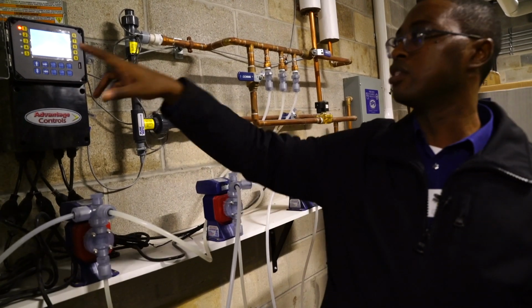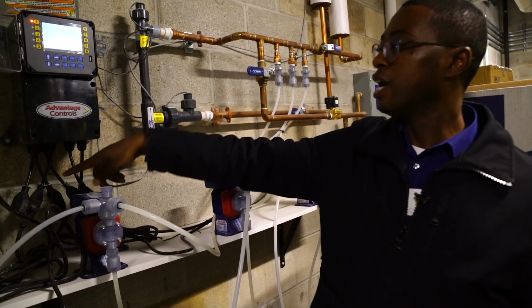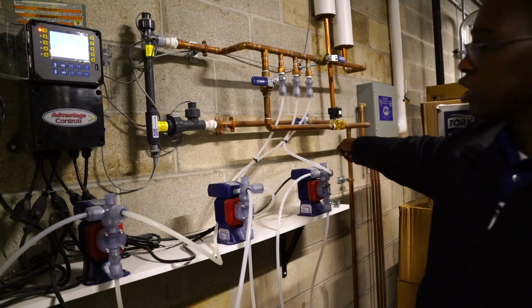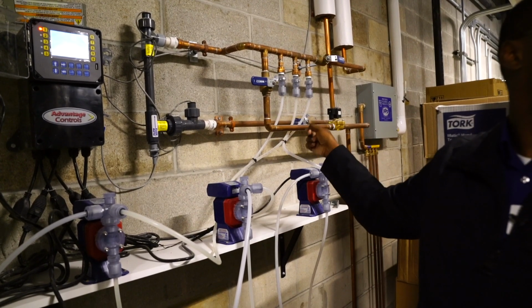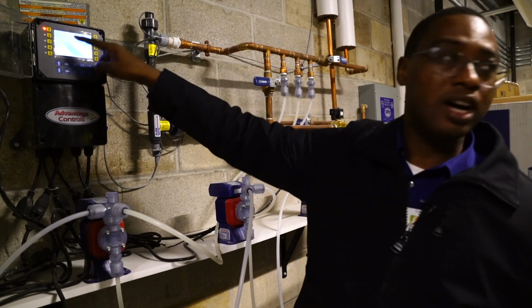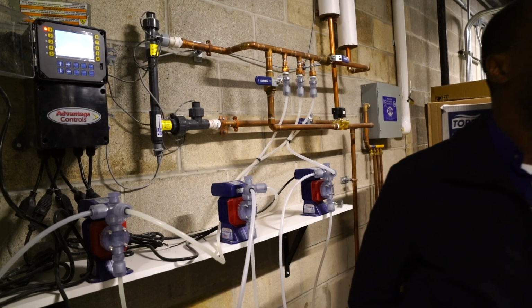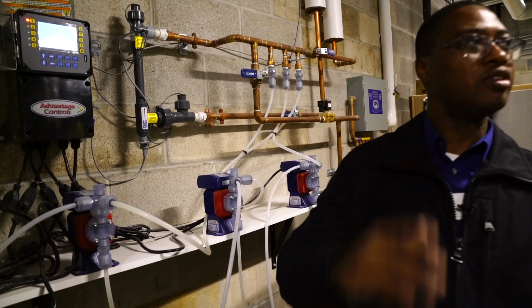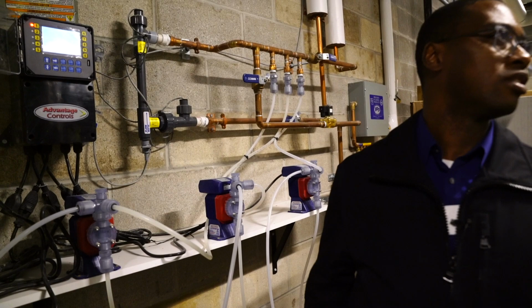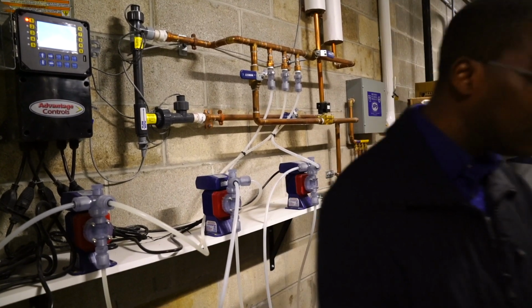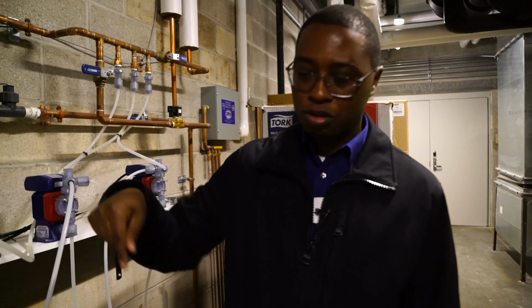So my guy comes and says, 'Oh, so this relay one, when it's connected to the solenoid valve, this will be bleeding until the number gets below 1100, because the differential is 100, so 1100, then it stops.' So even if you come in and the water is just dripping, you'll wonder why it's running all the time—it's because that number hasn't gone down yet.